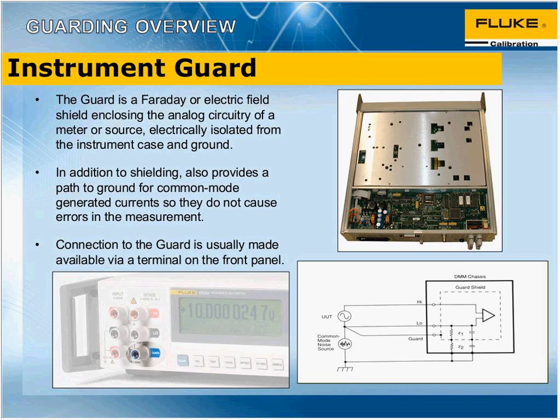This is where voltages will appear effectively on both the high and low side of our measurement, for reasons usually associated with capacitance in mains transformers and things like that. And by using a guard terminal connected to that metal shielding, we can encourage any currents that might be flowing in, which would be in our low lead and cause volt drops to appear in the resistance or inductance of that low side lead. Those currents can be diverted away harmlessly through the guard and not appear in series with our measurement circuit. And the guard terminal is the one usually appearing on the front panel of the instrument.